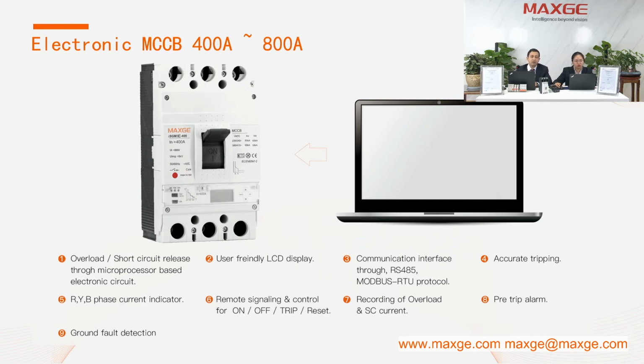And the second one is the pre-trip alarm function. The advantage of the pre-trip alarm function is that the MCCB will give an alarm in advance before it trips, so that it is convenient for the end user to know that the MCCB is going to trip and something is faulty in the network, so that the technician will go in time and attend to the fault.